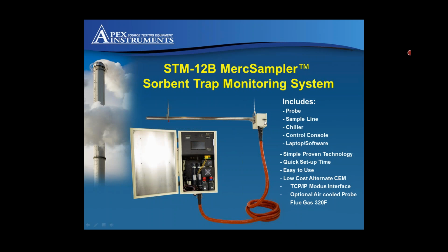We'll have what's called a probe heater, a secondary heater, coming from this way for the back end of the probe. The reason that we separate these two is that, especially where you guys are up in Michigan, if you're outside and you have part of that probe sticking out of the stack exposed to the elements, especially in winter, you might have a discrepancy between what the probe needs to heat on the back end and what it's seeing in the stack. So it allows us to ramp up the heat, make sure we're getting enough heat in the sections that we need to keep that sample above the dew point and protect the system from any moisture buildup.